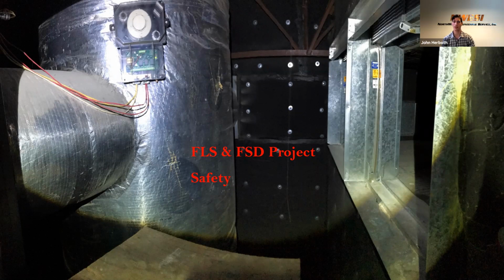In a lot of situations, we used to use a test magnet. You're not supposed to do that anymore for a functional performance test, though it's allowed for pre-testing. We end up smoking a lot of devices to get the first time testing done. In an existing building, you can go back to using a magnet unless it's an actual annual inspection with the authority having jurisdiction, in which case you need to use smoke again. So if it's not part of an AHJ's annual inspection, you can use a magnet, but for an annual or first-time functional performance test with a fire marshal, you have to use smoke.